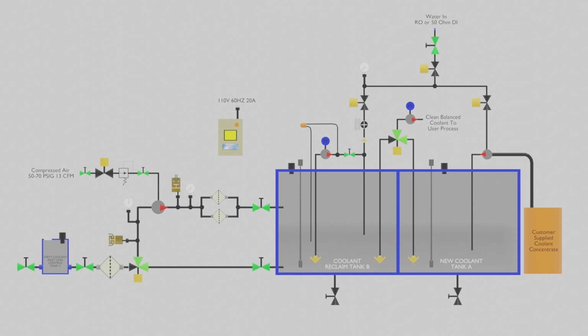Tank levels in both Tank A and Tank B are regulated by the auto balance controller, which receives signals from each tank's ultrasonic level detectors. To ensure fail-safe operation, pressure transducers in each tank also measure levels and serve as high and low level backups to alarm and prevent overfilling or underfilling.